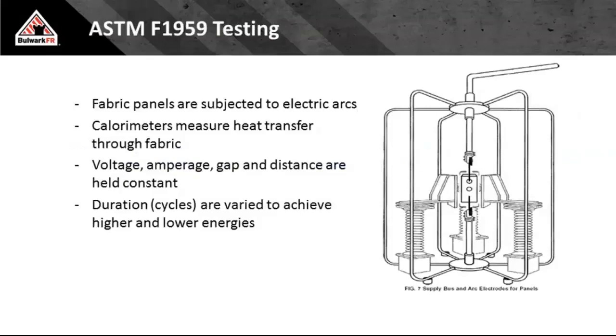What is the piece of equipment? What task am I performing? And then the tables will tell me approximately what PPE to wear. The other way to go about it is I go to Annex H and I apply the information in Annex H. Very, very rudimentary explanation. The two-step approach: I wear 8 calories of protection all day, every day, and or I climb into a 40-cal flash suit.